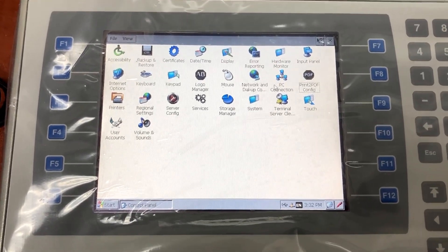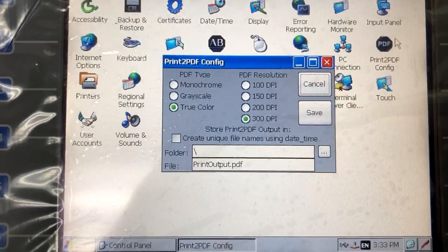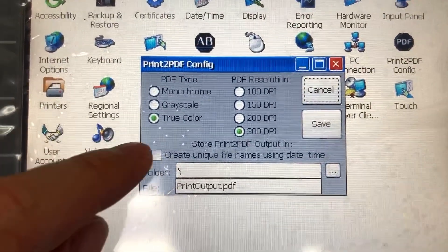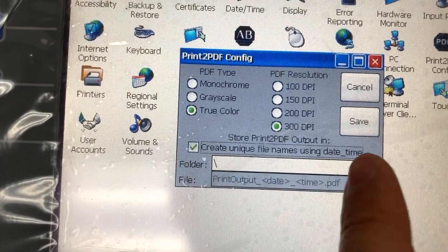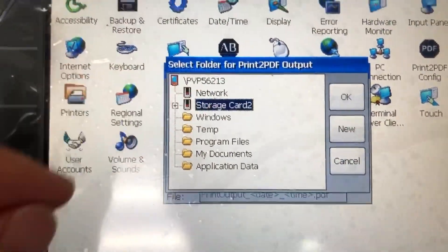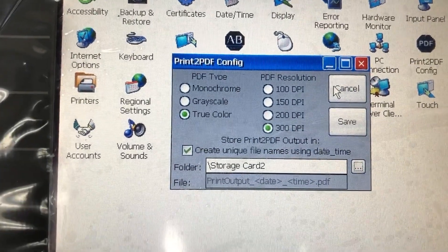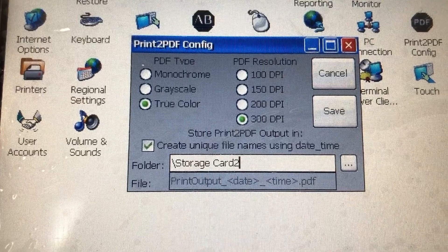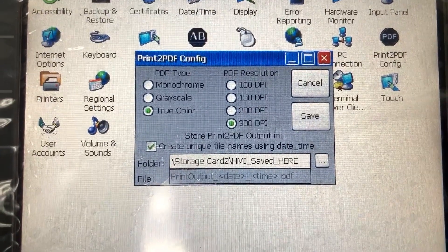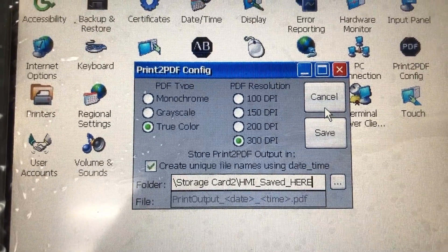In the HMI control panel, go to Print to PDF Config. Select 'Create unique file names using day and time.' Browse to the SD card — Storage Card2 is the SD card. Press OK. Using the USB keyboard, create a folder inside the SD card to store output PDF files. The name of the subfolder inside the SD card is 'HMI saved here.' Then press Save.